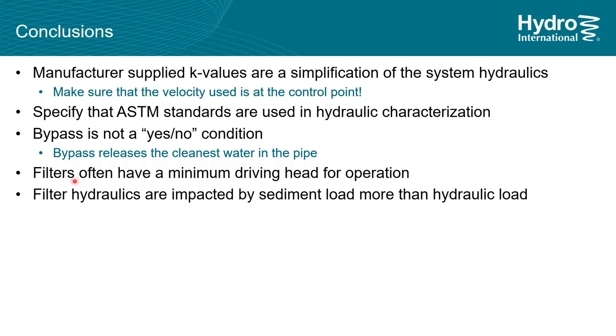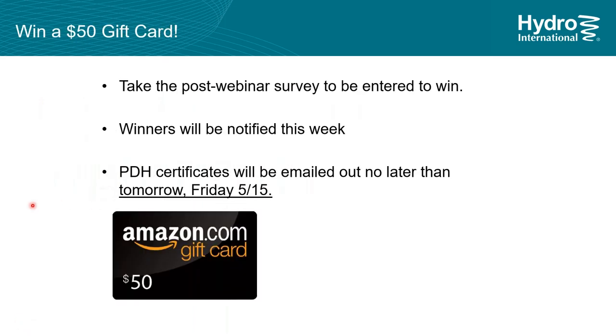When it comes to filters, they often have a minimum driving head as well as a maximum driving head, so you're going to watch out for that. And when you're talking about filters, the hydraulics of the system is more impacted by sediment load than the hydraulic load. So just a few things for you to take away.